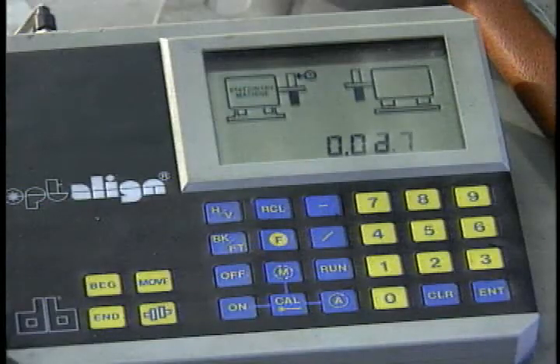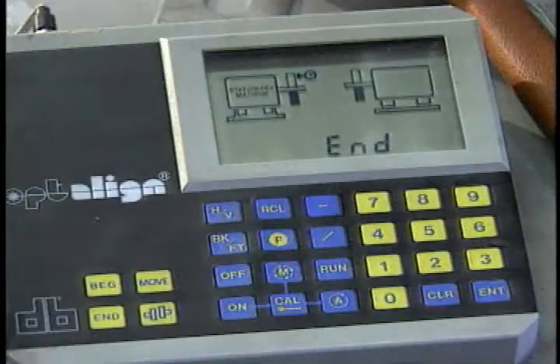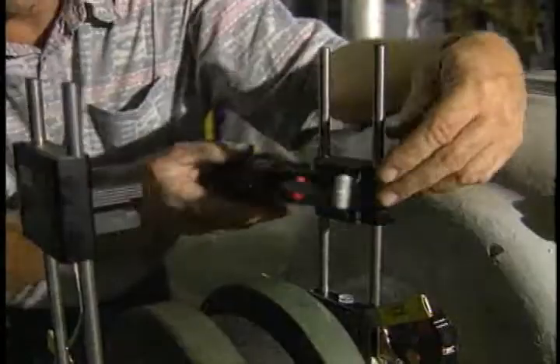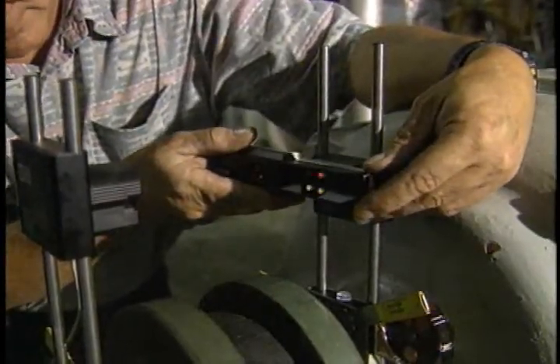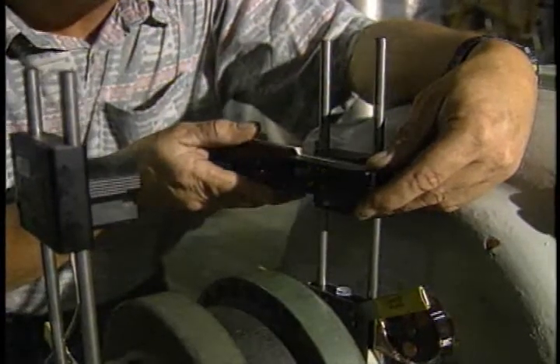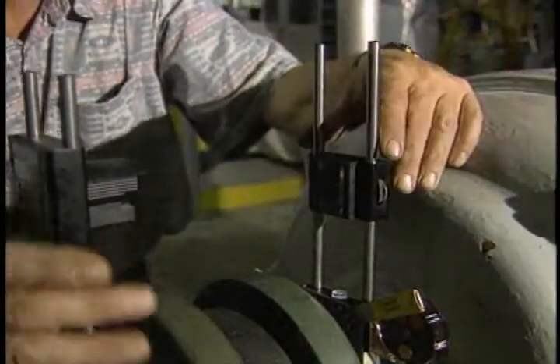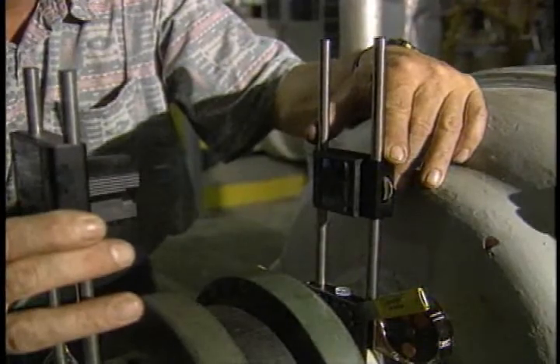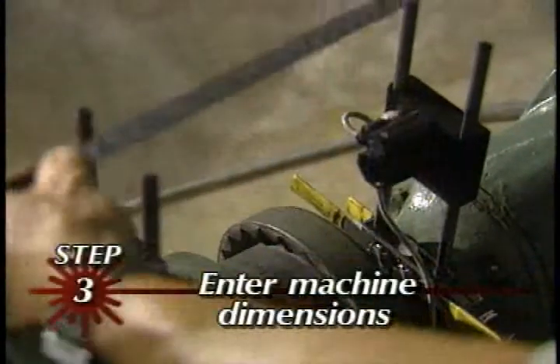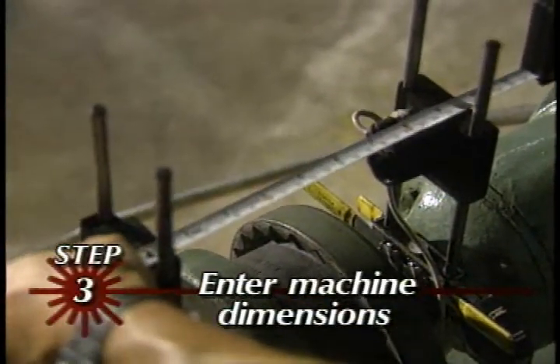Most computers will perform a systems check and report errors if any are present. Position the optic heads so that the light beam is striking the appropriate detector. This is when the beam finder may prove useful. Step 3 consists of entering certain measurements when prompted by the computer.